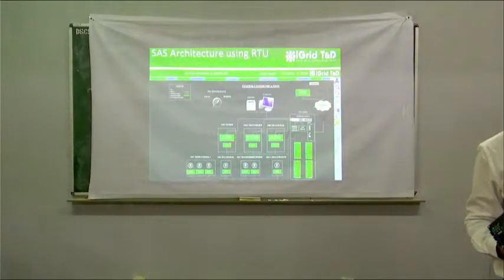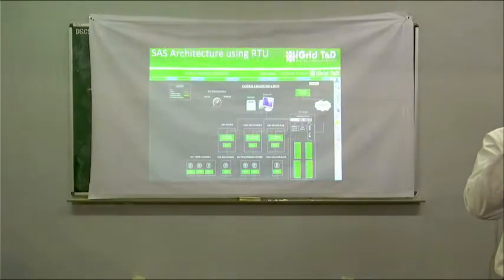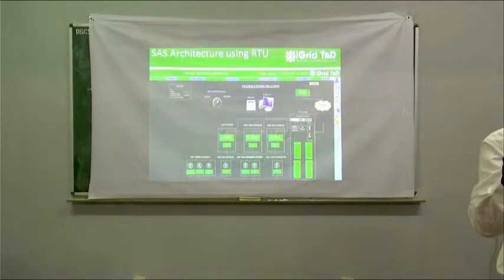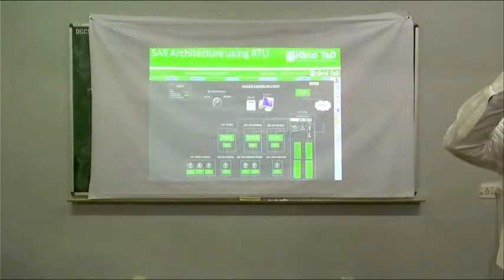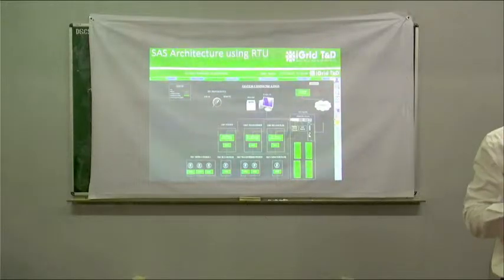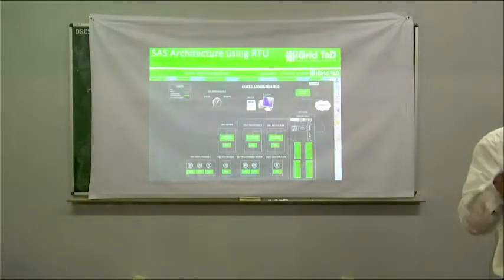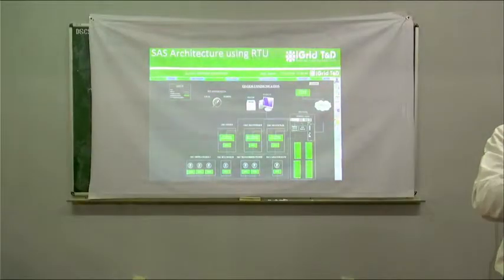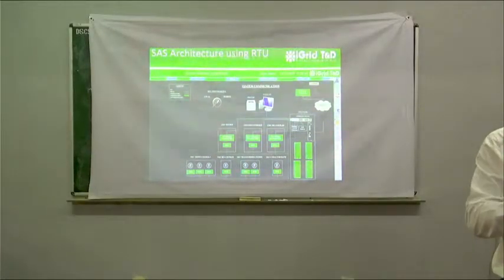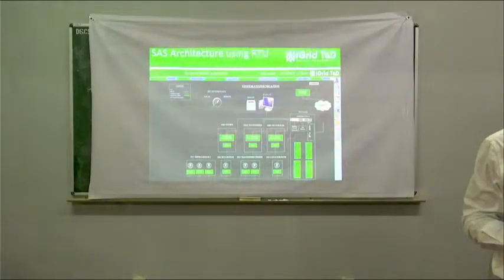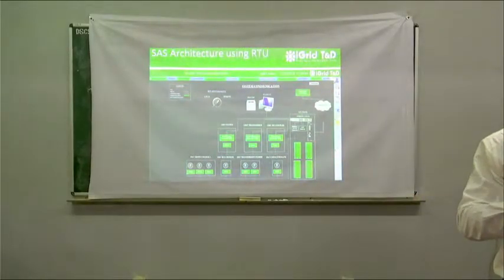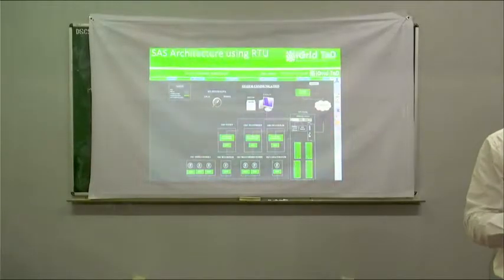In each of these control and relay panels, we give what is called a contact multiplier. Using the contact multipliers, whatever status is there, they would have given to their annunciator, where there is no SAS. To the annunciator, they would have given the breaker status, switchgear status, master trip relay status, all those things. What I will do is put this status to my contact multipliers, bring that wiring connection to my RTU panel, and then send that data using my gateway. That is how I convert my legacy substations into substation automation.